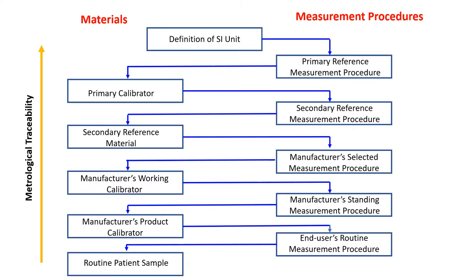This figure represents the metrological traceability chain detailed in ISO 17511. I am sure you have seen various versions of this figure and are familiar with the calibration traceability process, so I will not spend time reviewing the detailed specific steps involved. The essential components of the reference measurement system are the definition of the measurand, reference measurement procedures, and reference materials.